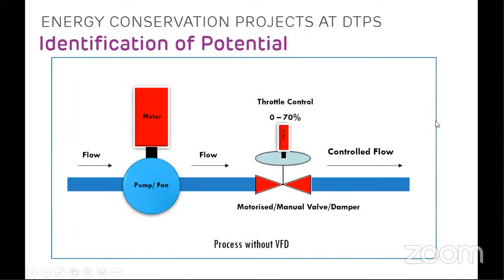I'll just explain how we can identify which motors we can install variable frequency drives on. If you go on installing variable frequency drives on every motor, then there will not be saving, rather there will be more initial cost and less benefit. So to identify which auxiliaries are suitable for VFD application, we carried out a survey.